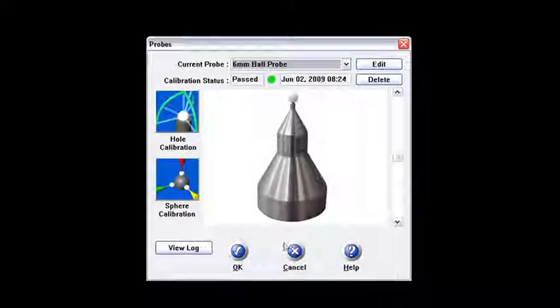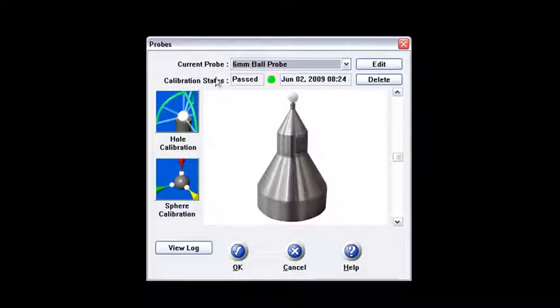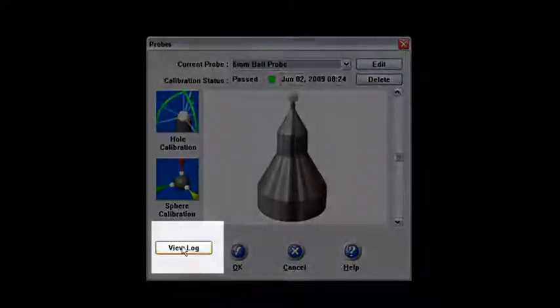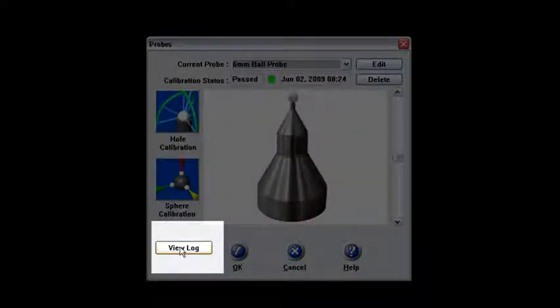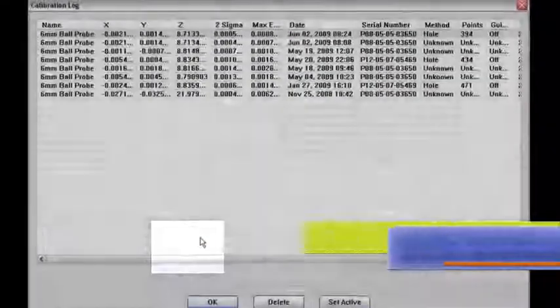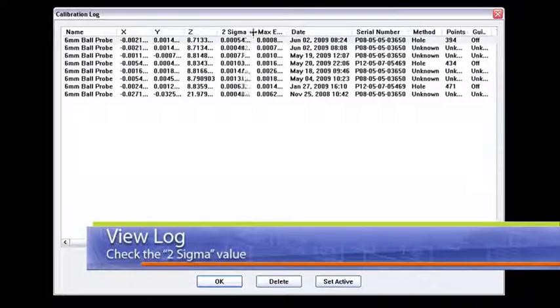The next screen that comes up again is this initial probe screen. What I like to do, even though I passed, I like to look at the view log. Once I click on the view log, it pulls up the values that it calculated for that calibration.